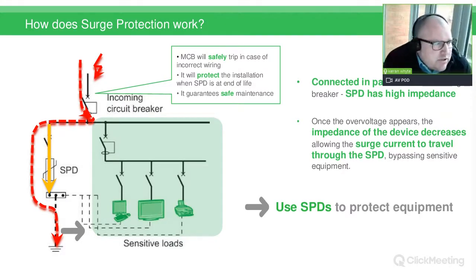So how does surge protection work? The surge protector sits in parallel to the load, and under normal circumstances it has a high resistance. Under fault conditions, that high resistance goes very low, and it drives the energy through the surge protection device away from your final circuits.